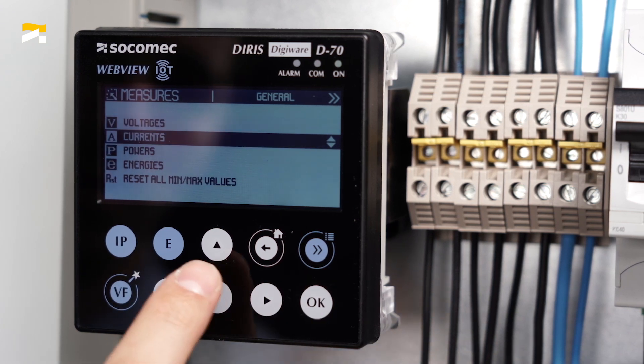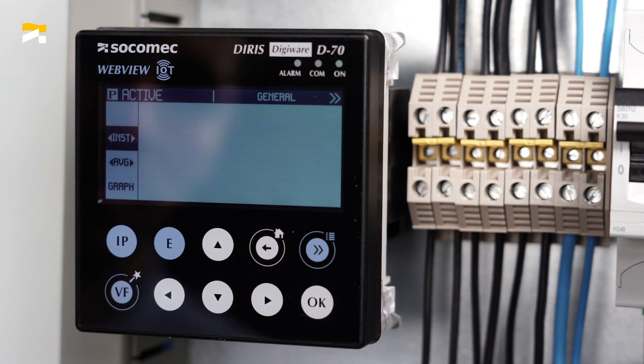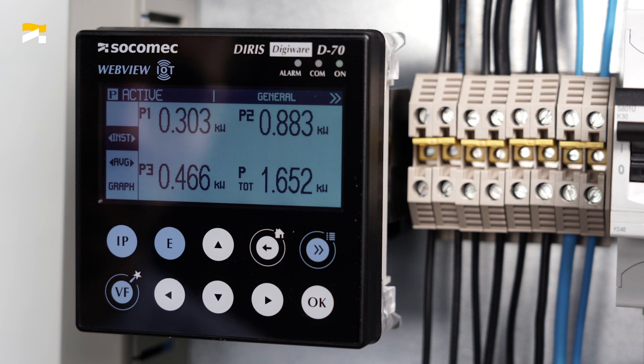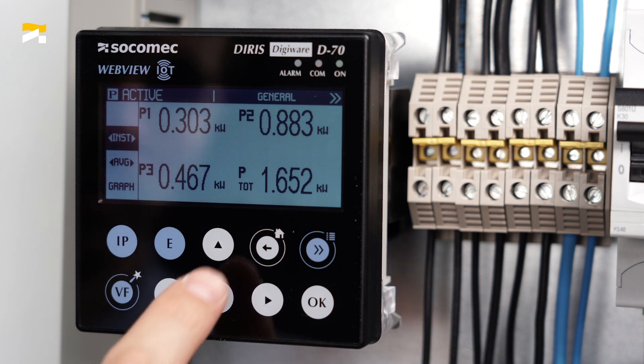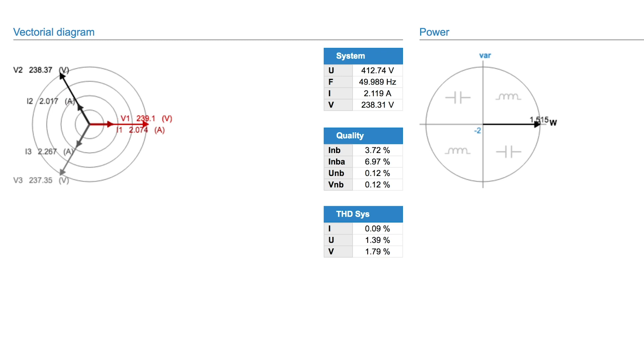Let's go back to the Measures menu. Power readings are now consistent. In the WebView web server, we can notice that all three phase currents and voltages are now in phase.